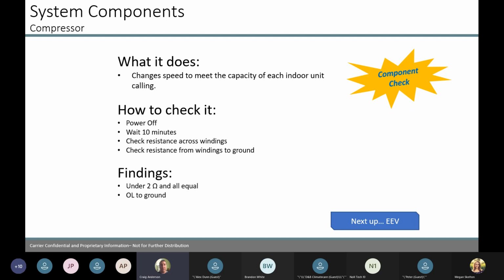So when we're talking about the compressor and the compressor's modulating, when you're doing service and you're going back and somebody else has done work to this unit and he's told you, I put some gas in it, I took some gas out. Save yourselves all the headaches, get the gas totally out of the unit and weigh it in. Adding gas and taking gas out when a modulating compressor is working is not telling you anything. You have no idea what stage that compressor is in to check what kind of pressures you have. Only way to check pressures on a unit is you need to know that compressor is 100% in full capacity at that point. If it's not, your pressures are not going to be correct.